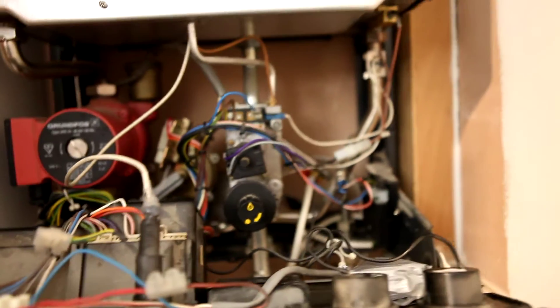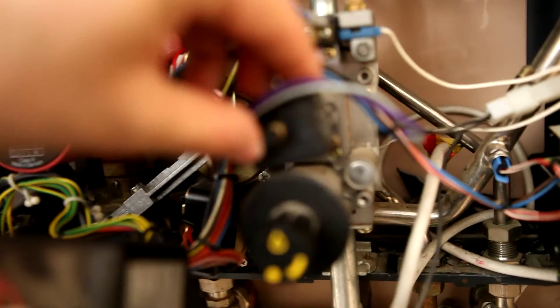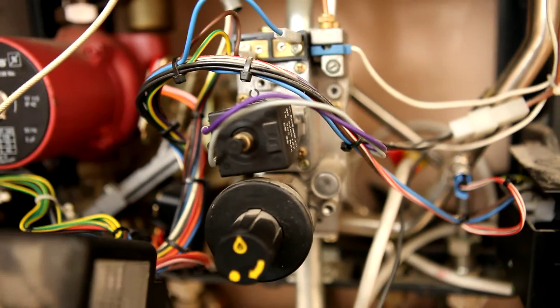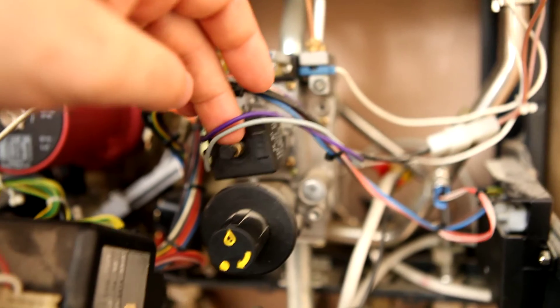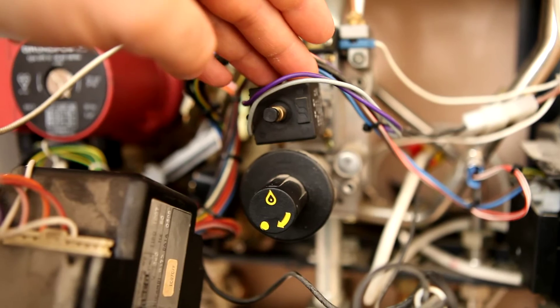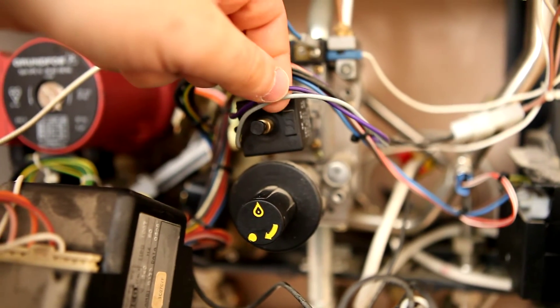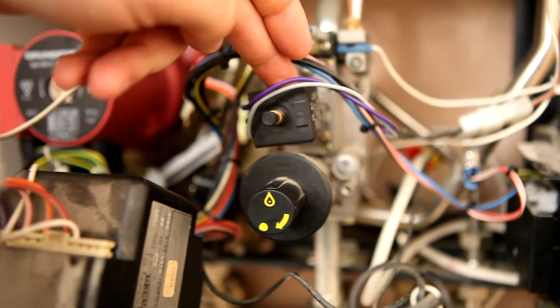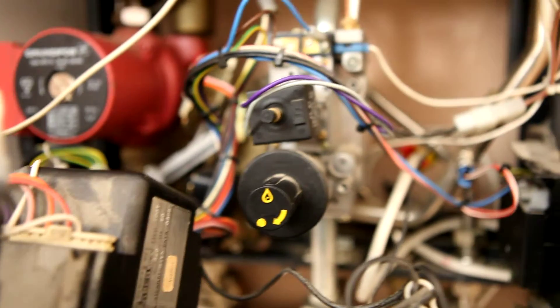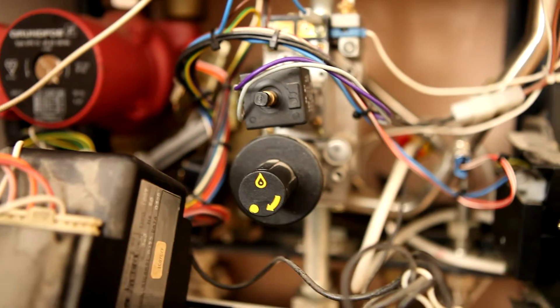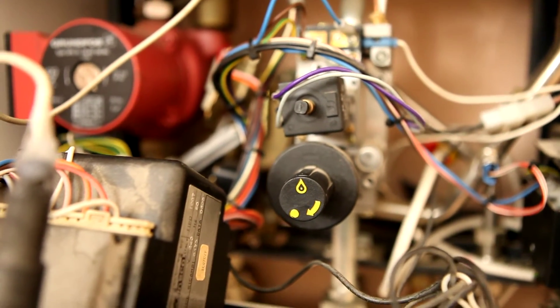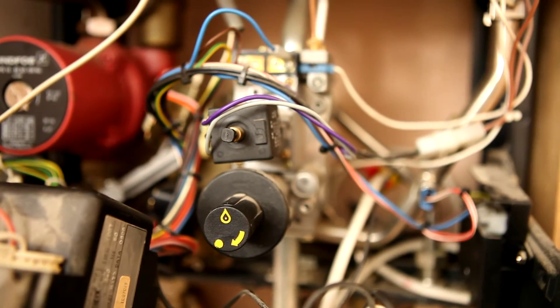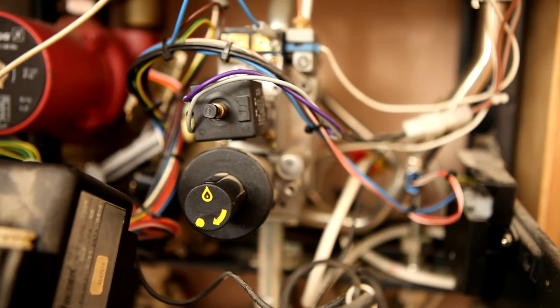So could it then be the gas valve pressure? This thing here is a little solenoid, and inside it there is a little brass tube, and in this brass tube is actually the gas pressure regulator valve. What happens is normally the gas pressure is on minimum, and then when a voltage is applied to the solenoid, the gas valve opens further. So I put a DMM on the solenoid, and sure enough it shows voltage on when the water is cold, and then as the water gets hot, the voltage disappears, indicating that the valve should be switching to lower pressure, but the flame stays high.